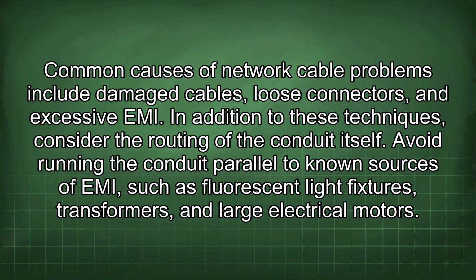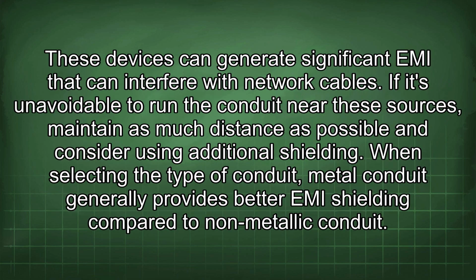Common causes of network cable problems include damaged cables, loose connectors, and excessive EMI. In addition to these techniques, consider the routing of the conduit itself. Avoid running the conduit parallel to known sources of EMI, such as fluorescent light fixtures, transformers, and large electrical motors. These devices can generate significant EMI that can interfere with network cables.